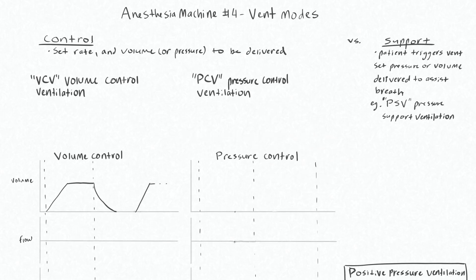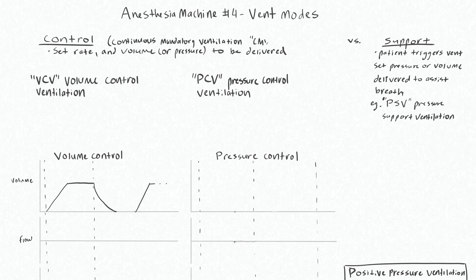One of your first decisions when you choose vent mode is whether you choose a control mode or a support mode of ventilation. For the control mode, what you're doing is setting a rate and volume or pressure that is to be delivered to the patient. Classically this is called a continuous mandatory ventilation, or CMV.